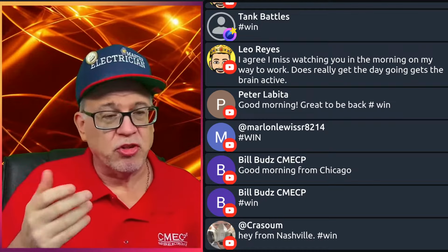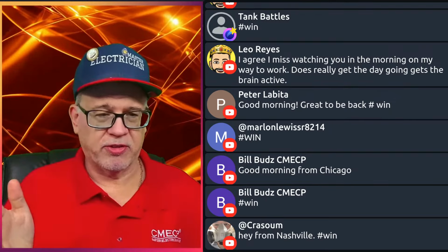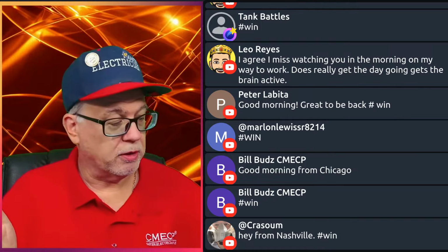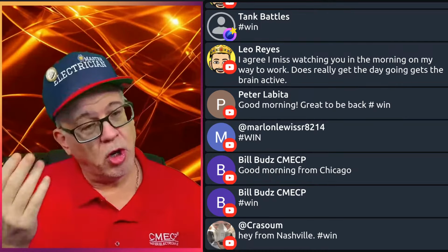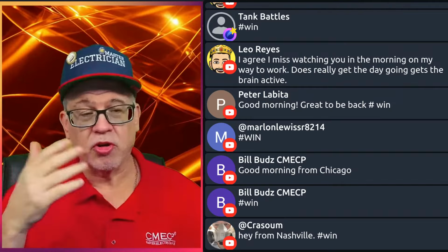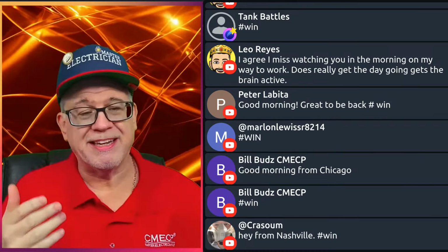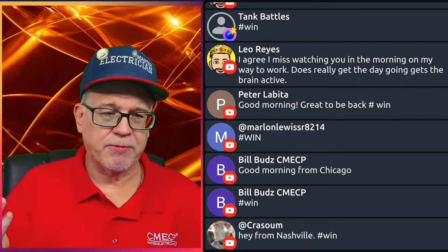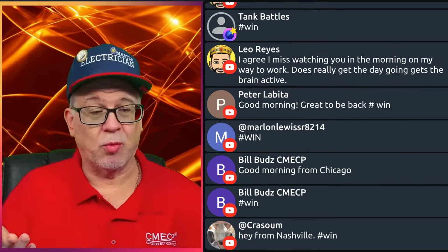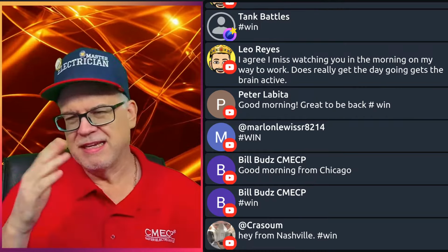So we just give that to you here to make life simple. We're telling you half horsepower, so that when you go to the tables, it's simple. But in the real world, you're still going to do that, because when you go to 430 to find out what the amps are for that half horsepower, it's going to be under the 115 column. That's why we do it here. It simplifies it and keeps it from being confusing for many people.